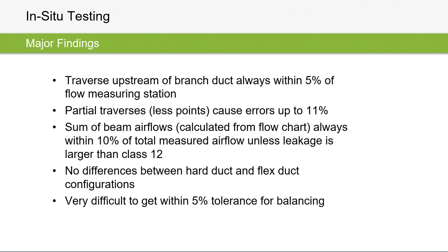And even in this little scenario that we mocked up, we still had a hard time getting within 5% of the tolerance. So it can be very challenging to get very, very accurate at these low velocities, low airflows, and higher static pressures. So that's our mock-up there.